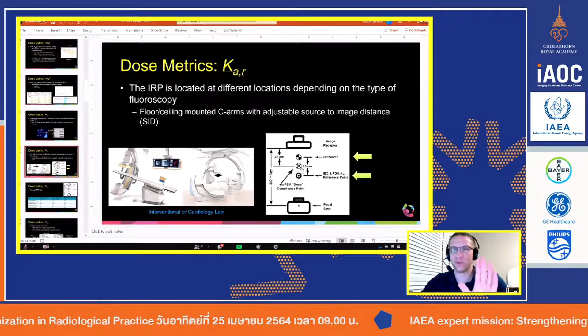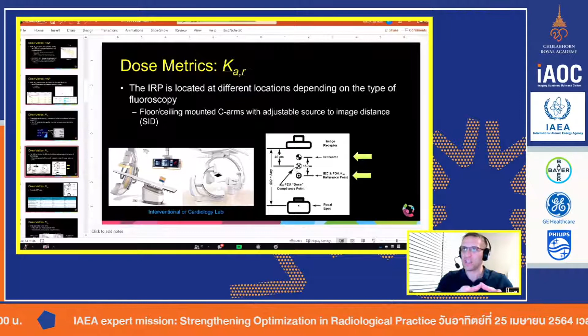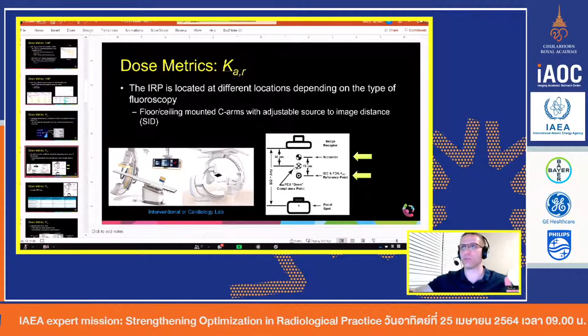Now, if you want to make it just super simple, you could put it at isocenter. But like I said, just be consistent. Because this value is a value you're comparing every year. You just want to make sure that machine is the same year to year. And if you do the same measurement on machine A and then machine B in the next room, that's a good way to make sure your rooms are giving you about the same radiation dose, going from room A, room B, room C, all the way down the hallway. So whatever you do, just be very consistent, and that should help you compare all of your values.